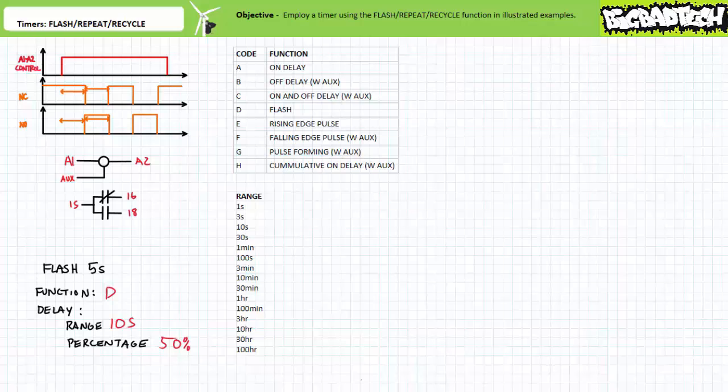You'll note timers executing solely the on delay or solely the off delay sometimes get their own schematic symbols. However, timers executing the flash function are often represented schematically as regular normally closed or regular normally open contacts. The documentation associated with the ladder logic diagram should clearly indicate that these contacts are performing the flash function. Let's now move on to the remaining topic of this lecture, putting a timer executing the flash function to use.